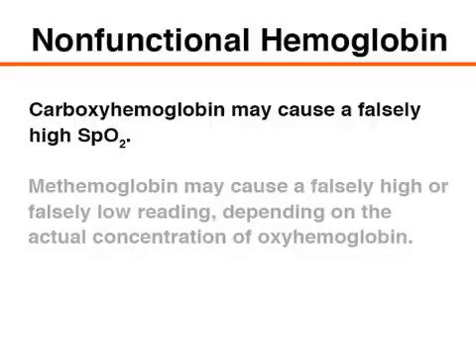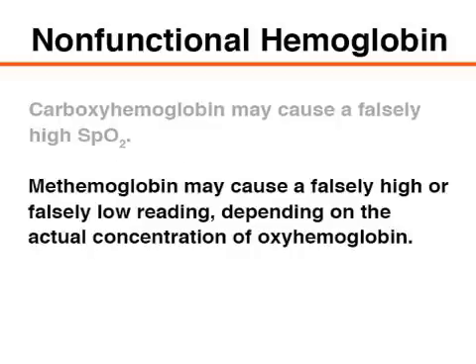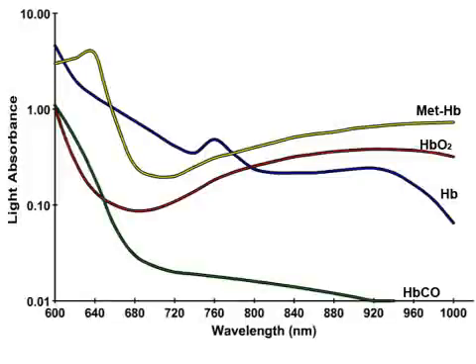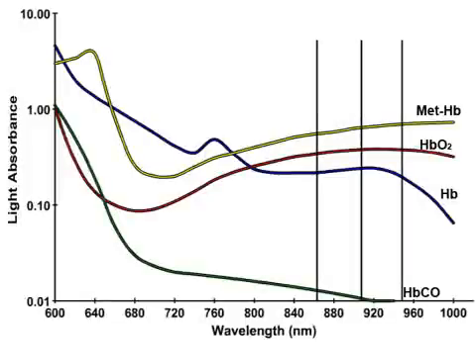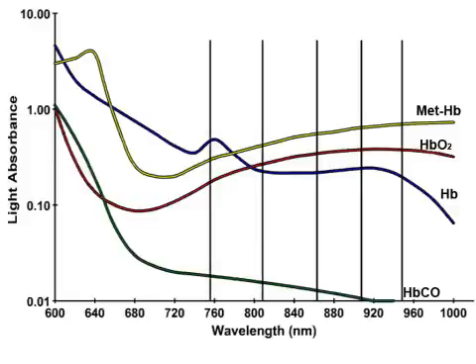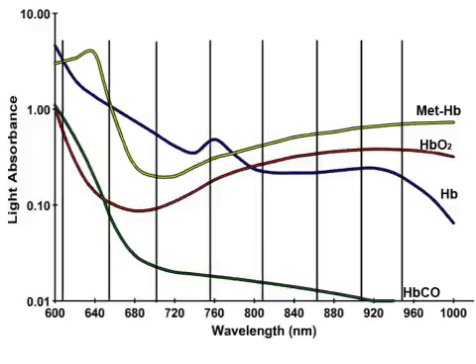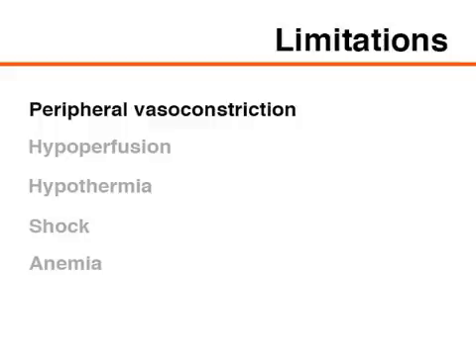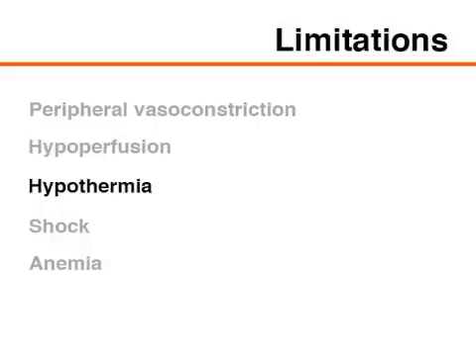Carboxyhemoglobin may cause a falsely high SpO2, whereas methemoglobin may cause a falsely high or falsely low reading, depending on the actual concentration of oxyhemoglobin. Newer pulse oximeters are able to emit light at up to eight different wavelengths, making it possible for the oximeter to distinguish carboxyhemoglobin and methemoglobin. There are additional limitations: peripheral vasoconstriction, hypoperfusion, hypothermia, shock, and anemia may also yield inaccurate results.